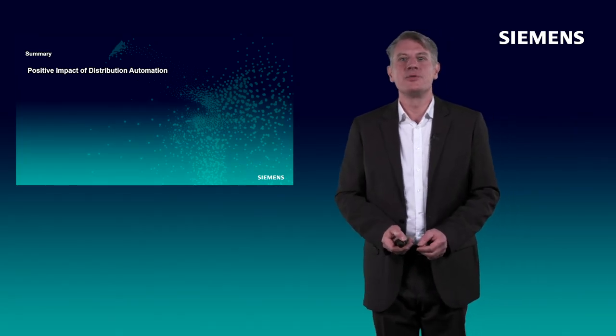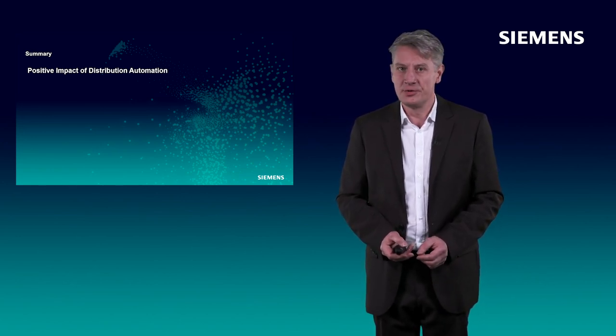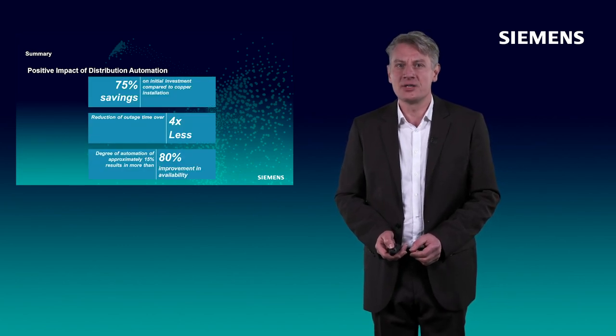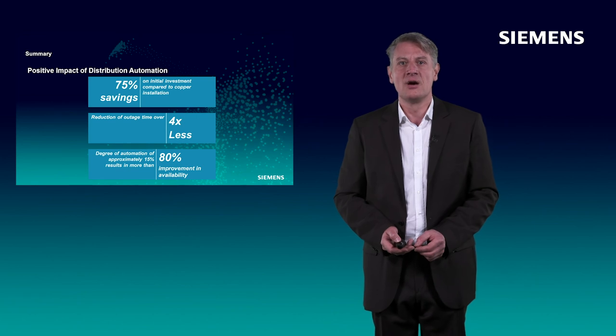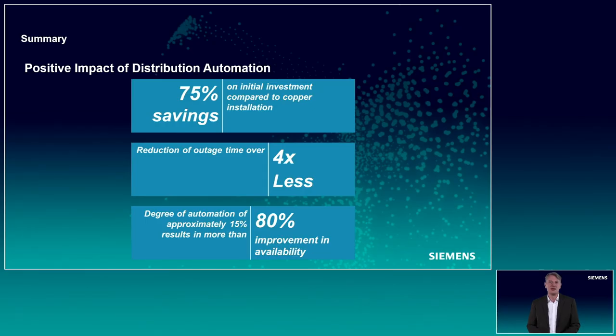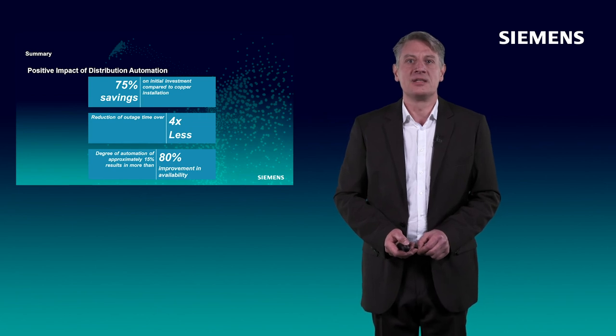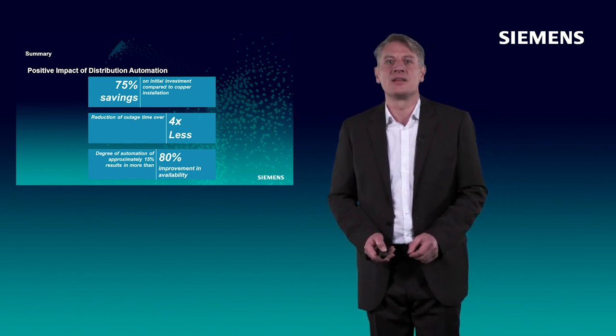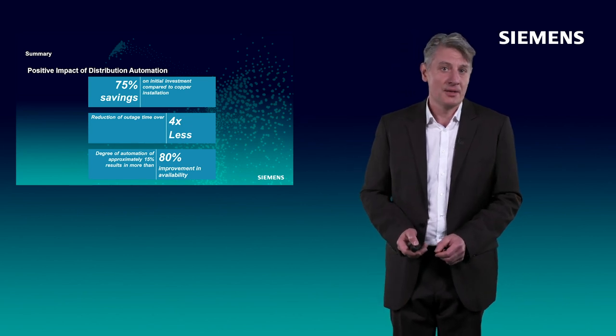Let's come to the summary. Distribution automation has a positive impact on the reliability and efficient operation of distribution grids. Impressive figures are measured in our pilot project combining distribution automation devices with the closed-loop application of the self-optimizing grid: 75% savings in comparison to the initial investment compared to copper installation, a reduction of outage time of more than four times, and a very impressive figure — a degree of automation of approximately 15% results in more than 80% improvement in availability. Thanks a lot for watching. That was my presentation.